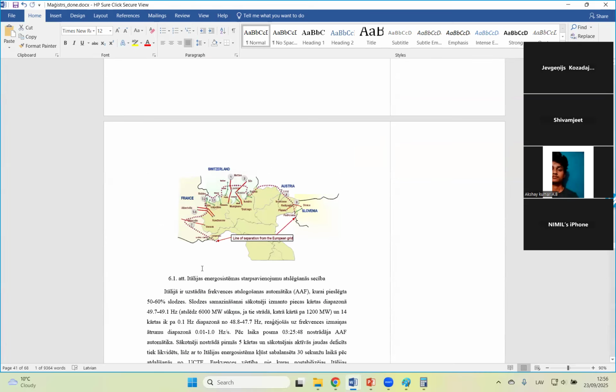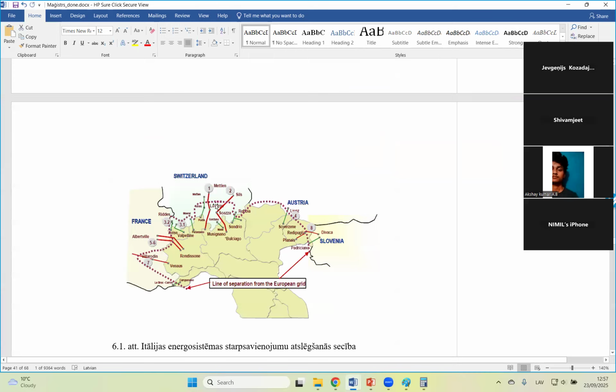In this case, we need to go to the map. Okay, what do we see? One line is off, but we still need to import 7 gigawatts of energy. That means that other lines that are still in operation must transmit more power. As you know, more power, more current, more heat, and as a result, problems with wire length. And as a result, after some time, the temperature of the second 380 kV high voltage line increased, wire length increased, and a new touch to a tree. As a result, one more very high voltage line disconnected.